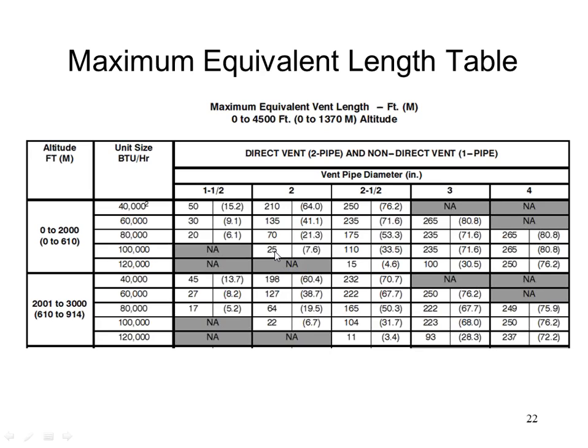So I could probably get 10, 15 feet of pipe and a few handful of elbows and stay within this 25-foot number here. Or I can go up to 2.5-inch pipe, which I probably wouldn't do because that's a rare pipe size and probably costs more than 3-inch pipe does. So I would go with the 3-inch, and in that case I can go 235 feet. And with 4-inch I can go 265 feet. So that's pretty long distance, and you can see for all these sizes, 250, 265, 265, 265, and 250. So every size can vent up to 250 feet with the right size pipe on it. That's a pretty long distance, and that's a one-way trip from the furnace to the exterior. So in a two-pipe design, this fan can basically handle 500 feet. It'll have 250 feet on the intake and 250 feet on the exhaust. So that fan can speed up to take care of what it needs to take care of.